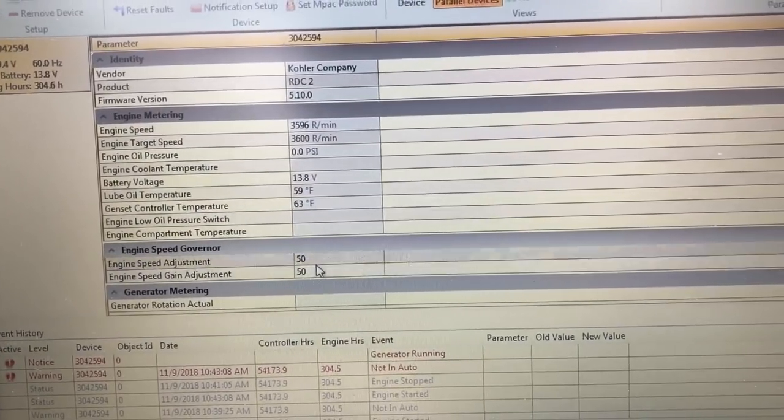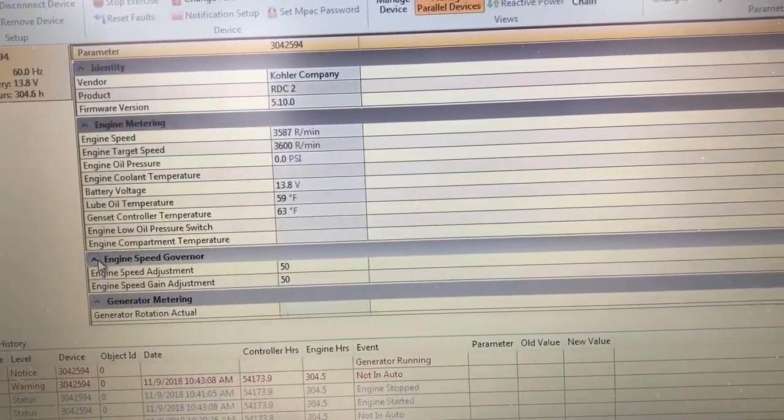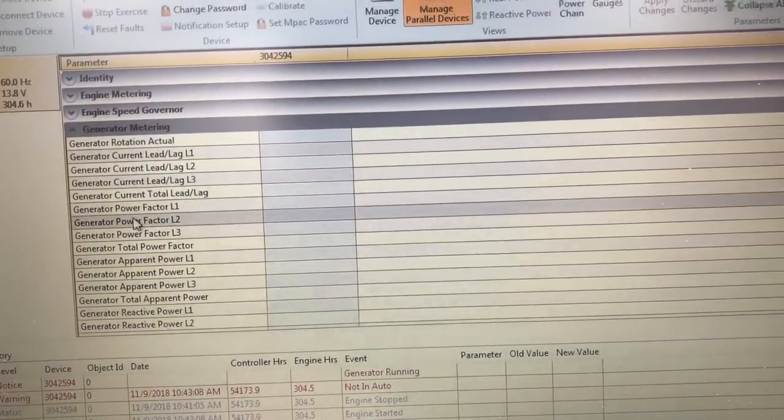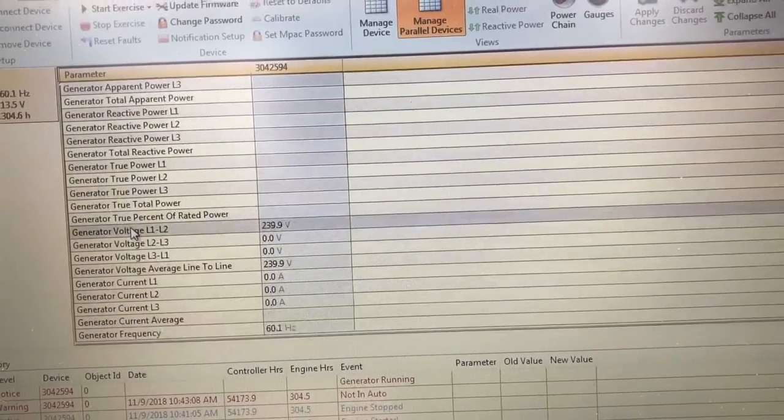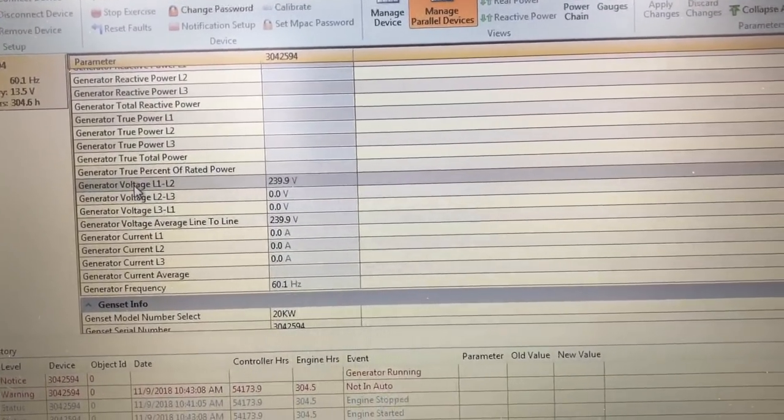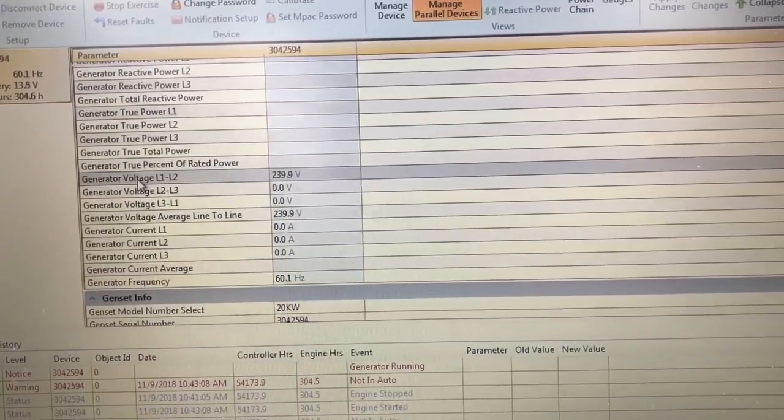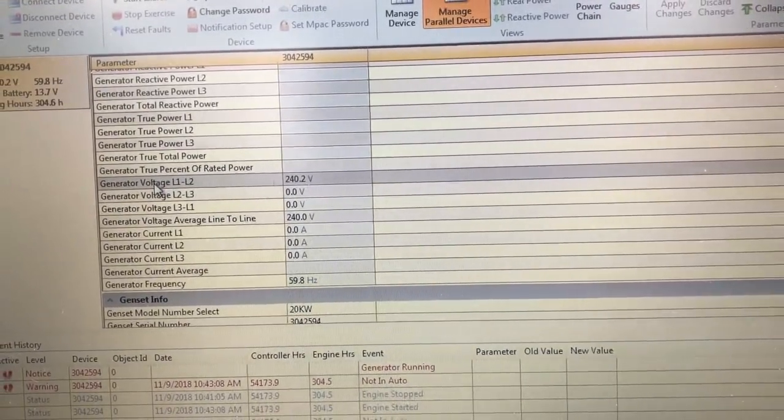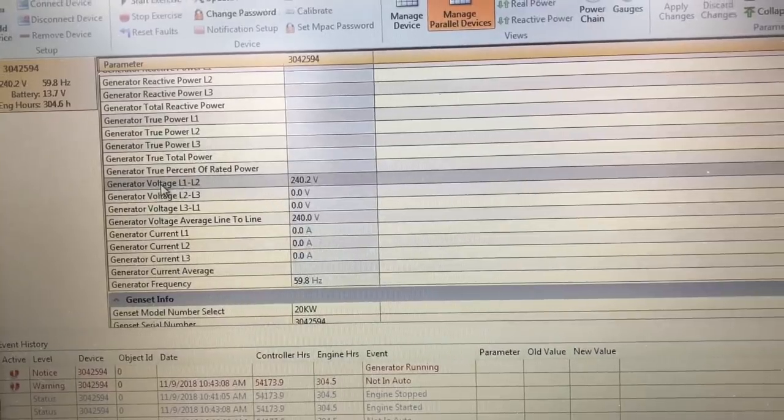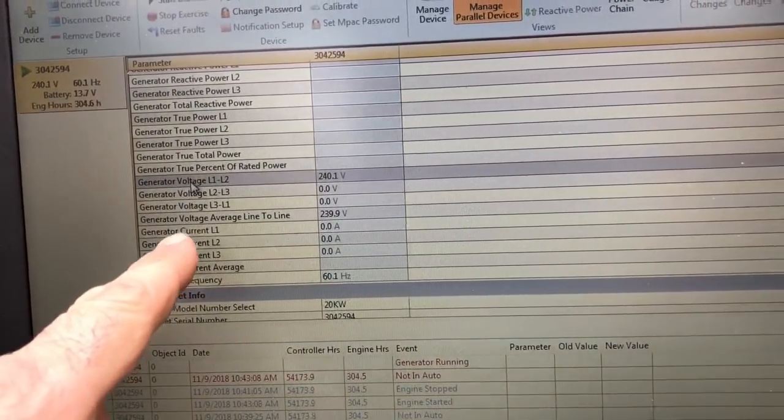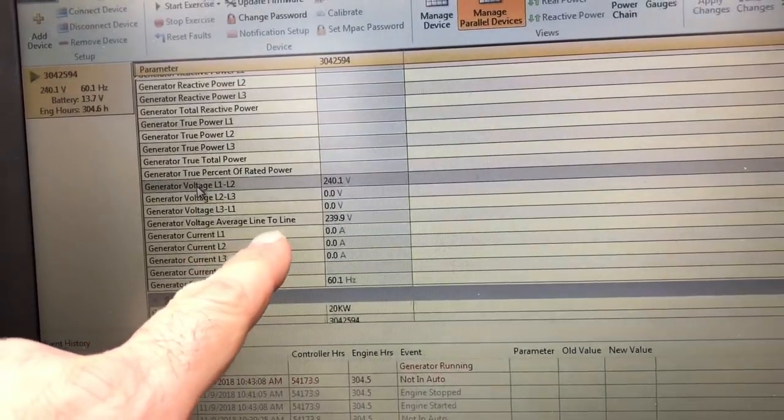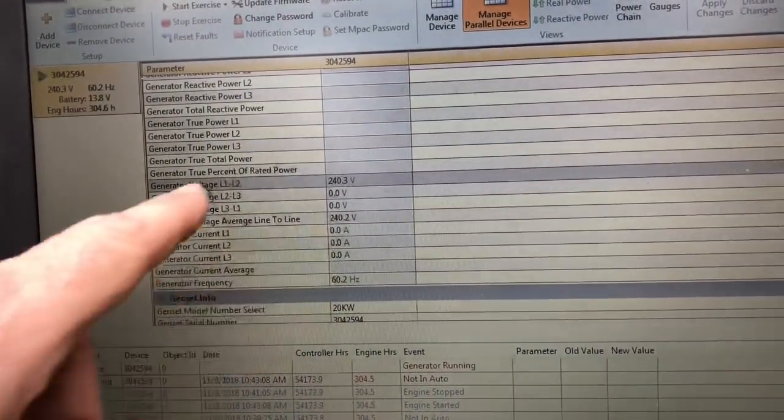My engine speeds, I'm not going to be making any adjustments with those. Those are the menus I don't need. My metering, my generator, I'm producing 239.9 volts on L1 and L2. I'm a single phase, I don't have L2 to L3. As you can see, my generator voltage average line to line is about 240.